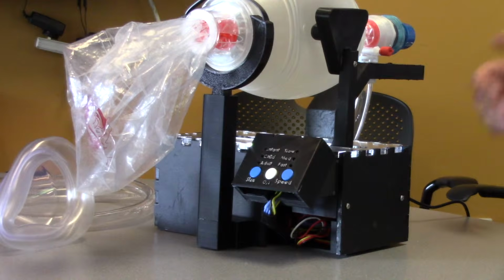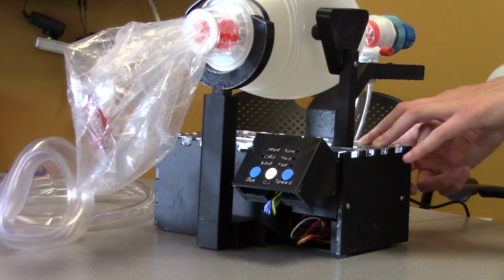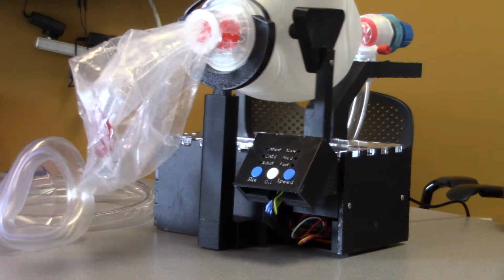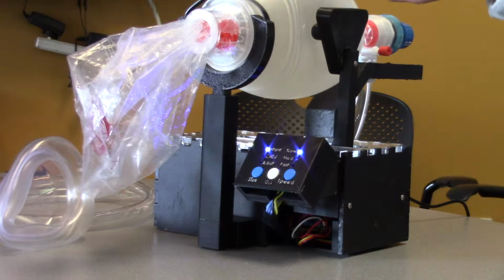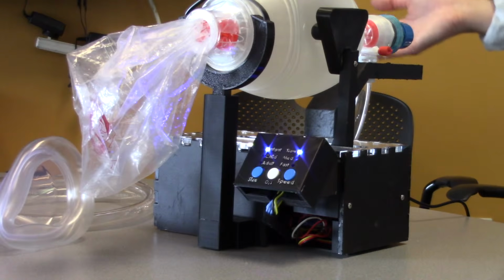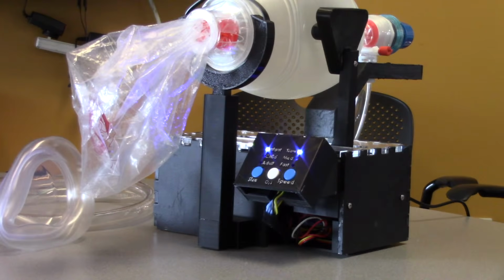In order to initiate the compression stroke, you first turn on the device, and it goes through a calibration sequence in which it closes the bag completely and opens it. That will allow the motor to know the full range of motion.